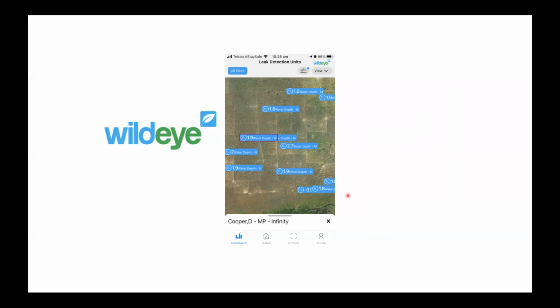So if we look at this system here, we can see this one here is reporting 0.9, which is telling us that we've got a problem with that sensor. The normal reading depth is about 3.5 meters on the sensors we use, and most tanks are only about 2 meters deep. So if the sensor fails and it goes beyond the maximum reading depth of the tank, so it's reading 3.5, we know that we've got a failed sensor as well. So the daily messages are a great way of monitoring a healthy system, if you're just waiting for a low level alert, it may never come if the system is offline.